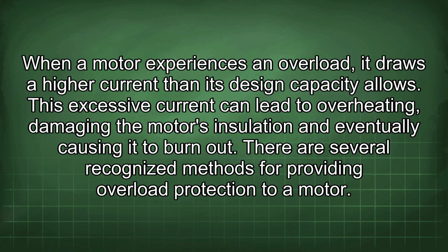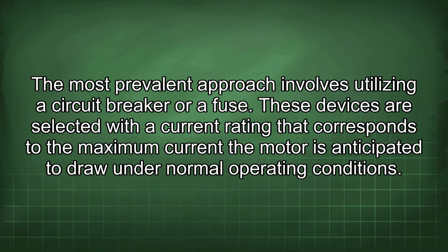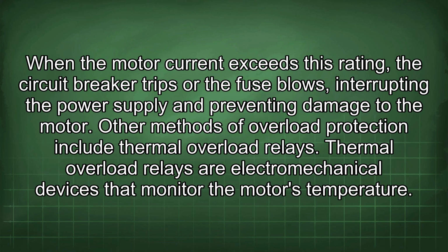There are several recognized methods for providing overload protection to a motor. The most prevalent approach involves utilizing a circuit breaker or a fuse. These devices are selected with a current rating that corresponds to the maximum current the motor is anticipated to draw under normal operating conditions. When the motor current exceeds this rating, the circuit breaker trips or the fuse blows, interrupting the power supply and preventing damage to the motor.